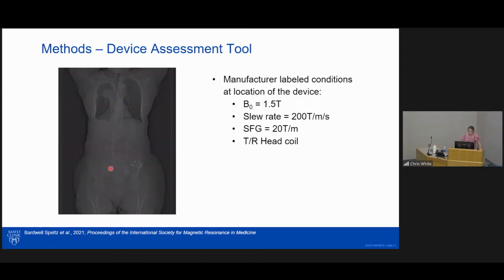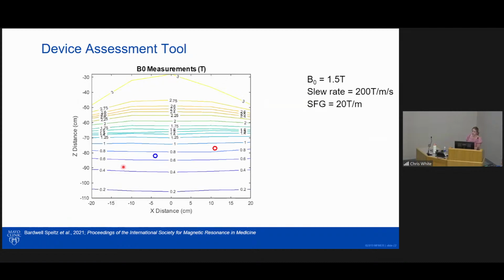The manufacturer labeled conditions for this device, which means conditions at the location of the device, include a main magnetic field strength of 1.5T, a gradient slew rate of 200 Tesla per meter per second or less, a spatial field gradient of 20 Tesla per meter or less, and a head TR coil. So this shows the main magnetic field strength values. The specified location of the IPG is shown as a red circle, and the lead tips, or the electrode, is shown as the blue circle. Here we can see the main magnetic field strength is less than 1.5T at this device location. So we know this condition can be satisfied.